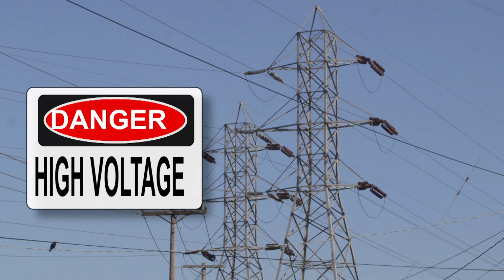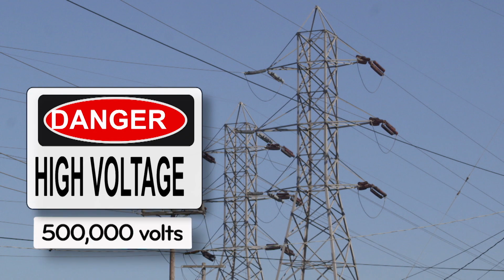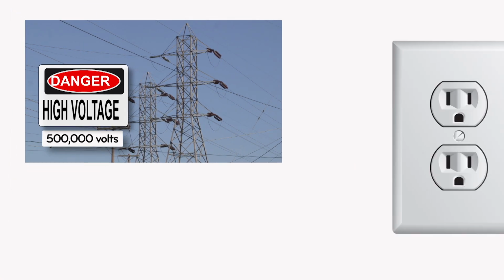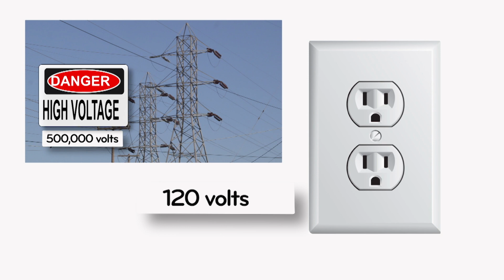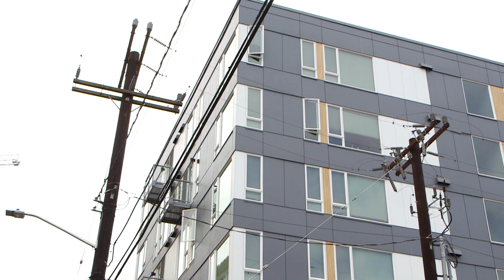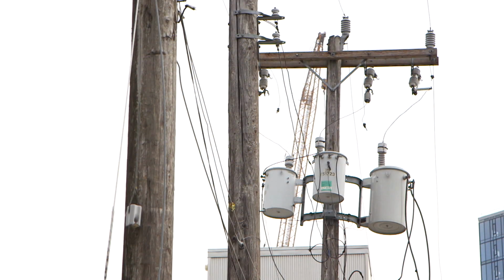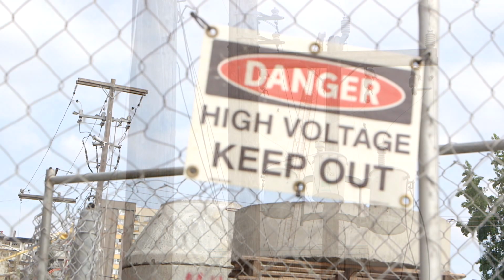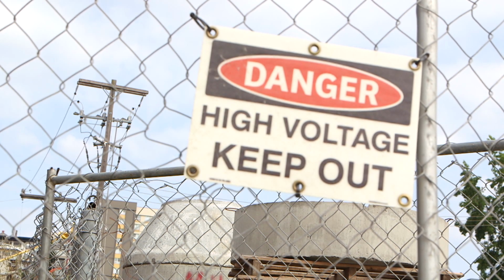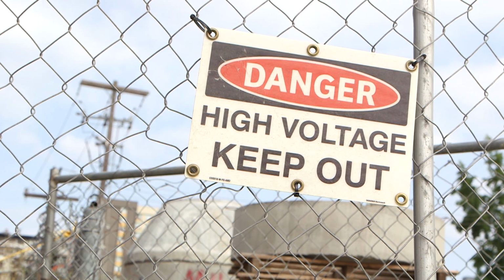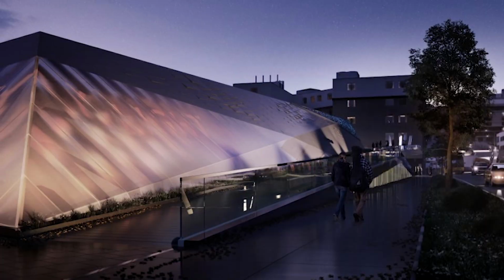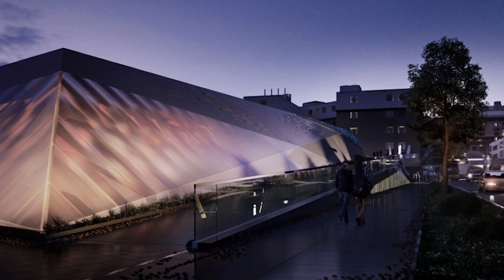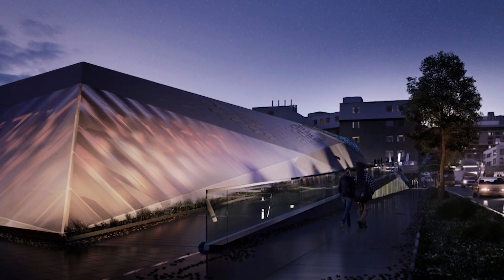Some high-voltage lines carry 500,000 volts. Compare that to your average electrical outlet at just 120 volts. The lines coming into Denny right now will be 115,000 volts. They will get reduced down to 13,000 volts for the circuits out in the street. And at the vaults, the transformers would then reduce it down to the voltages that the buildings require for their operation. The substation serves to provide safe transmission of that power.